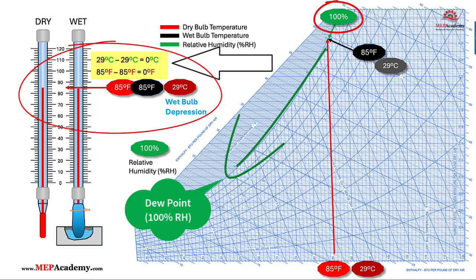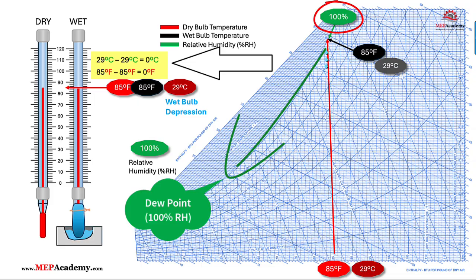Dew point is the temperature at which air becomes fully saturated — 100% relative humidity — and moisture condenses into liquid dew. If the dry bulb temperature falls to the dew point temperature, condensation occurs, leading to dew or fog. When the wet bulb temperature is close to the dry bulb temperature, the air is near saturation and the dew point is close to the current temperature, meaning high humidity levels.